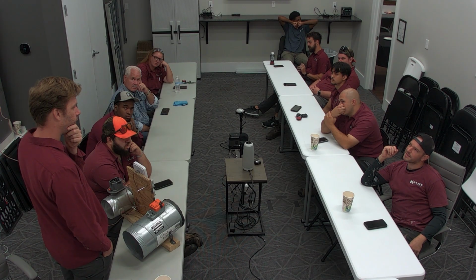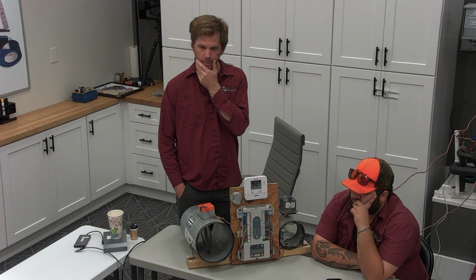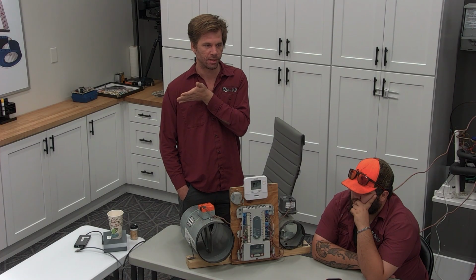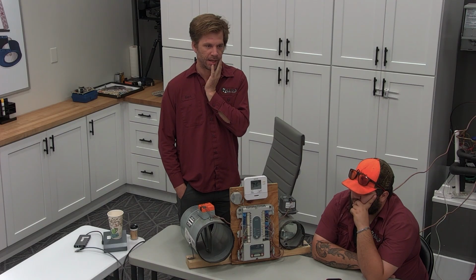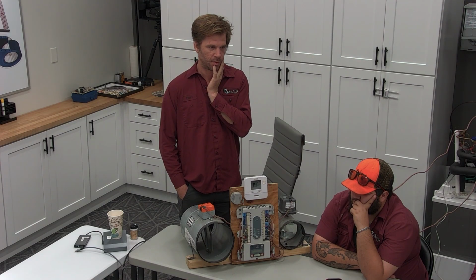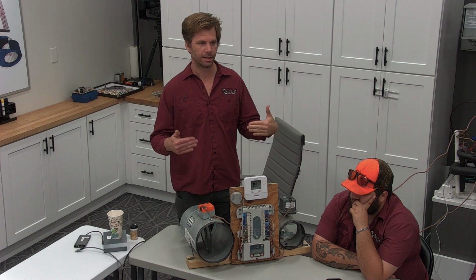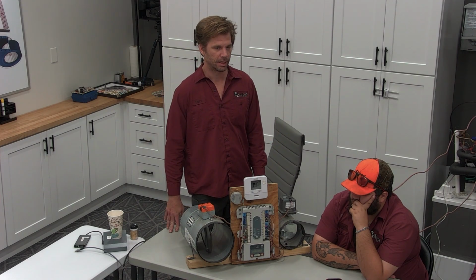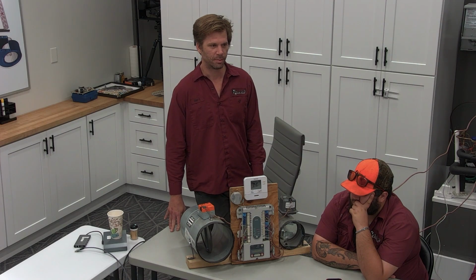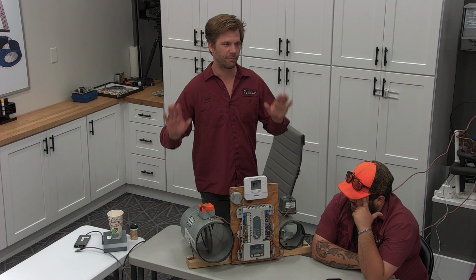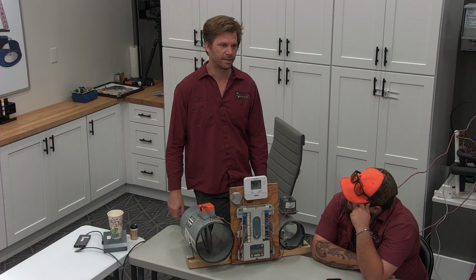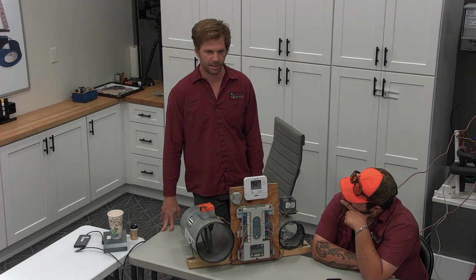That should be normal operation though. Normal operation is one shuts down and the other runs. Damper panel has failed closed. We have no airflow, even though it's calling for it to be open, the motor has failed. And we're running heat, electric heat pump, and it's pumping it against the flat wall. That's where the DAT sensor comes in and saves the day, saves the equipment.